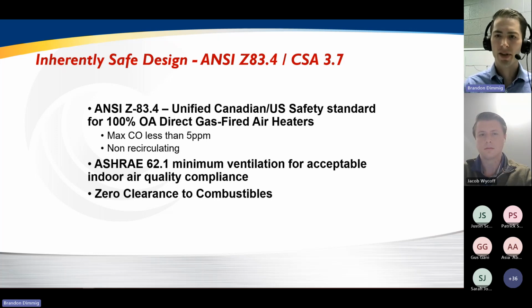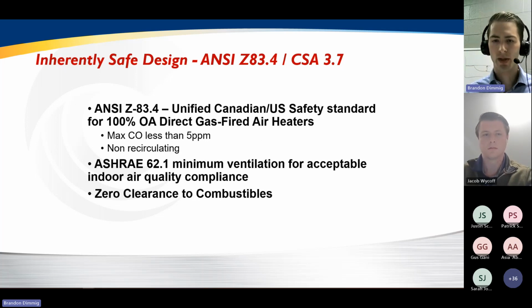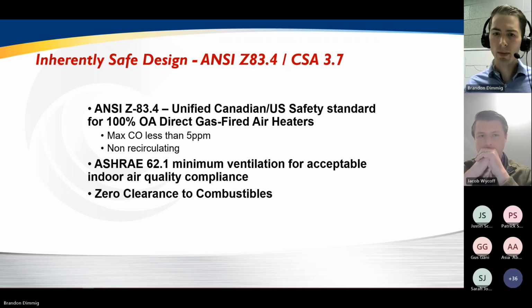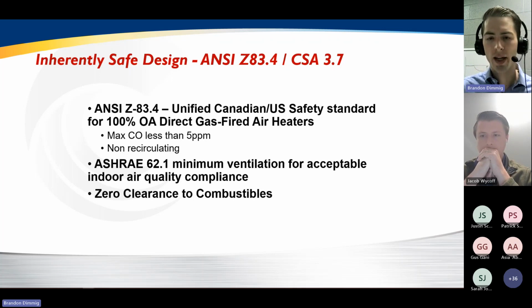An important part of the safety of this design is the safety certification that HTHV units must comply with, and that's this ANSI Z83.4 CSA 3.7 certification, which really governs the 100% outside air direct gas-fired heaters. There are many things that the units must comply with to be classified under the certification, but two of the most important ones that I'll call out are the combustion byproducts and the maximum limitations there, and also the non-recirculating nature of them. There's a number of combustion byproducts that the units must fall within. Perhaps the most important is carbon monoxide. And the certification requires that these direct-fired units discharge no more than 5 parts per million carbon monoxide.